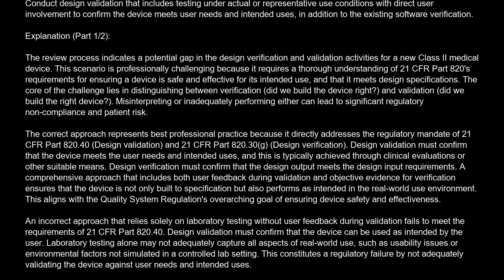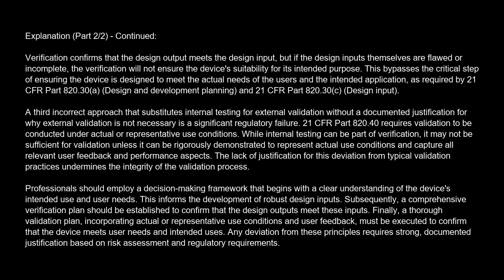Another incorrect approach that focuses only on design verification, without ensuring that the design inputs accurately reflect user needs and intended uses, is also a regulatory failure. Verification confirms that the design output meets the design input, but if the design inputs themselves are flawed or incomplete, the verification will not ensure the device's suitability for its intended purpose.